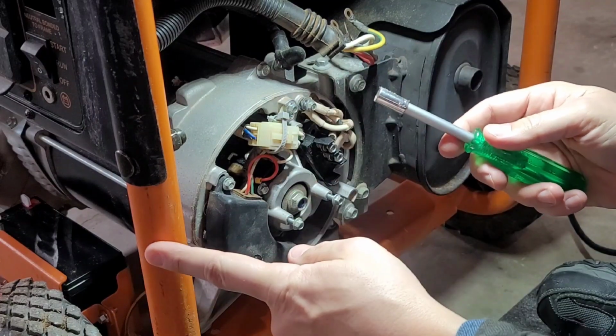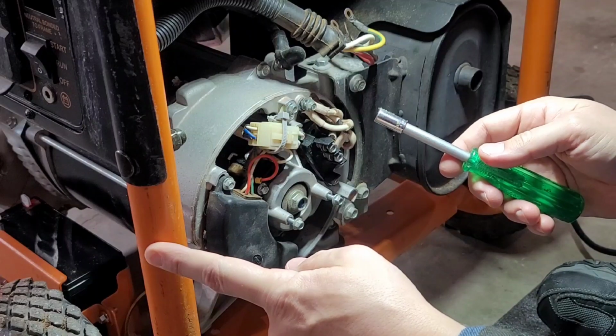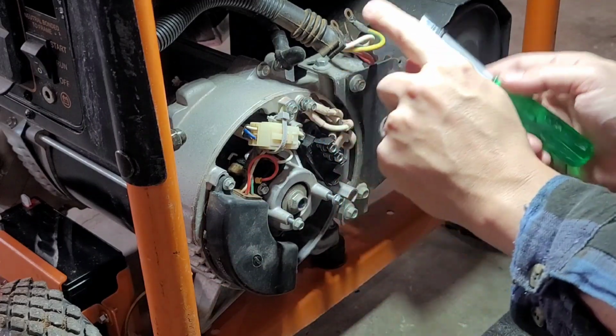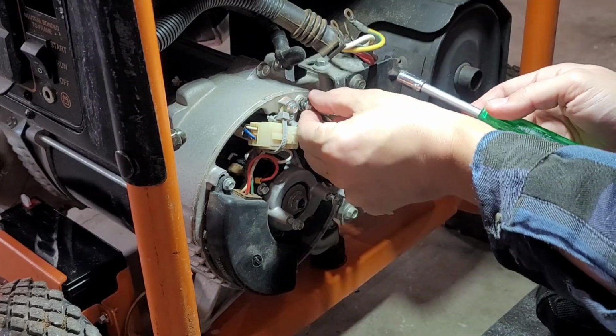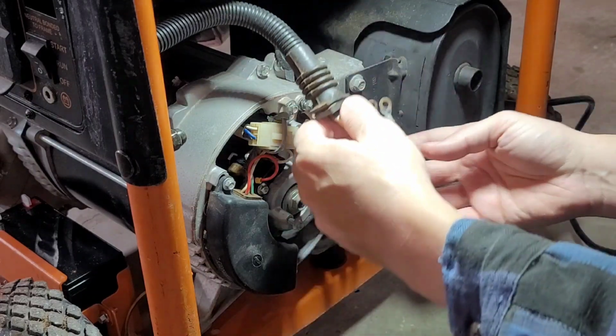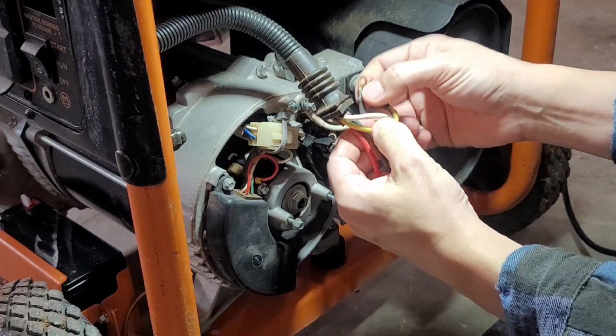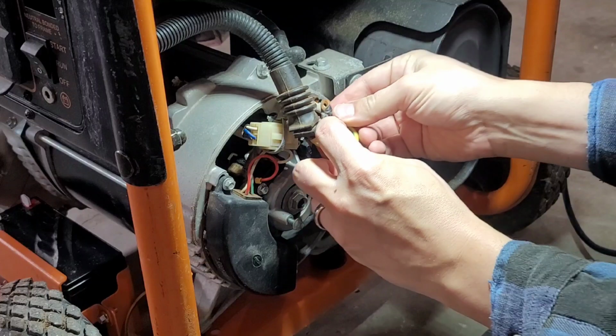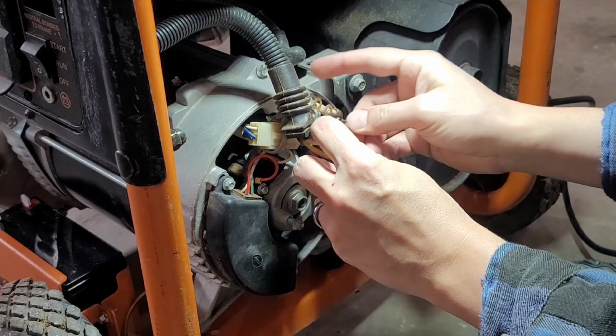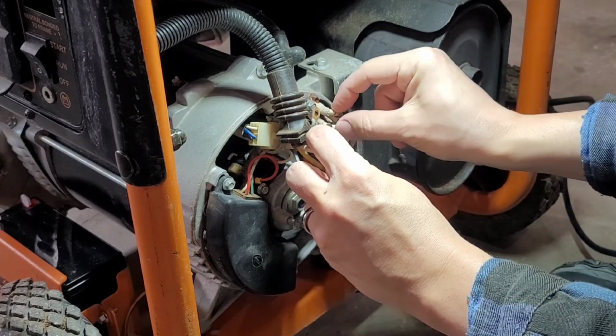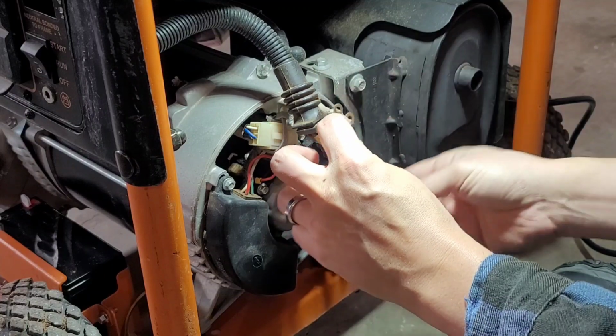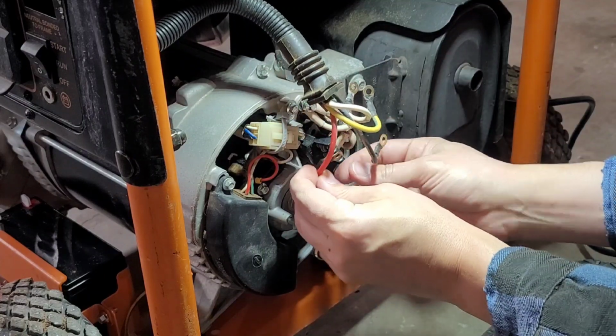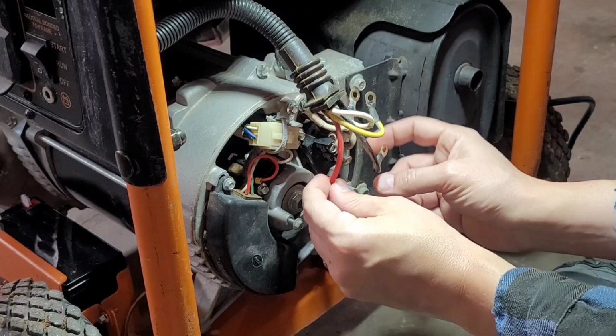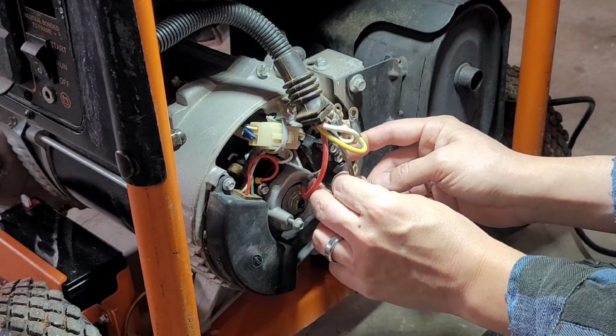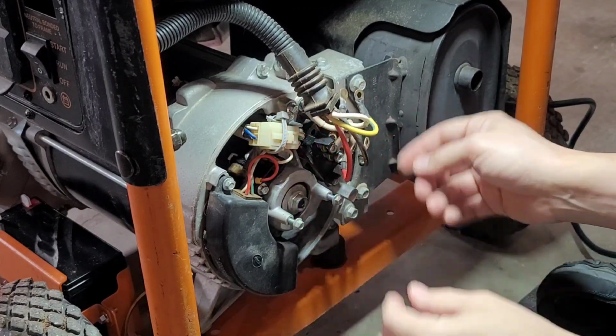Note that this is a generator where the frame is grounded to the neutral. That's important, because when we connect it here, the neutral, which is the white wire, and the green, which is the ground, are going to go to the frame screw right here where the other neutrals are coming out of the stator. We're then going to put the red wire on one of the hots, and the black wire on the other hot wire. So that's what we're going to do.